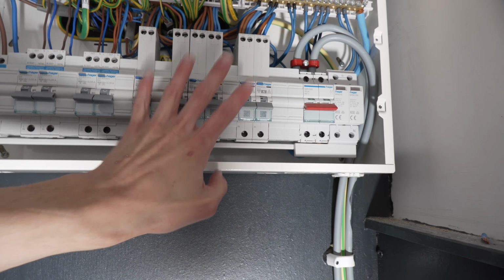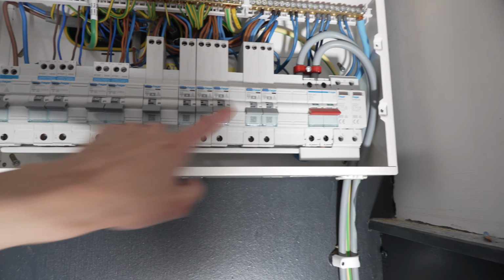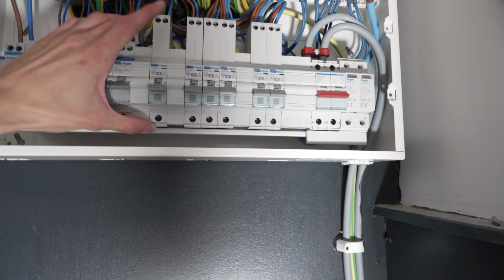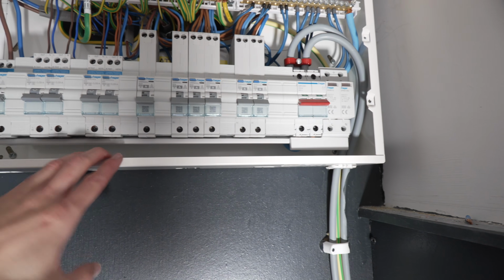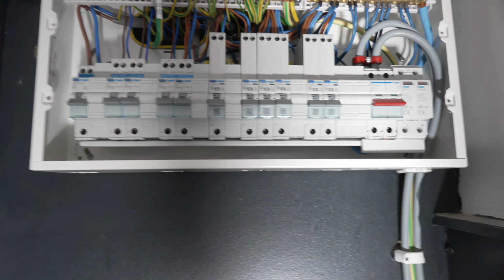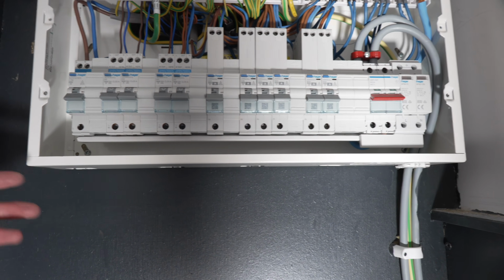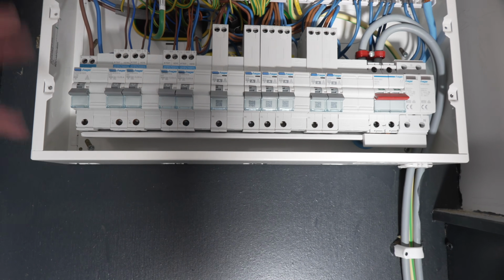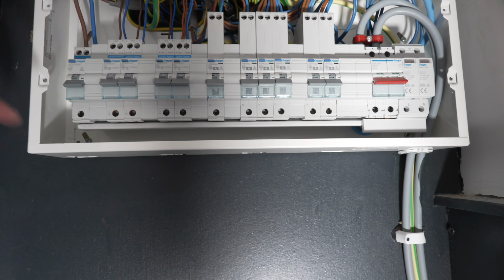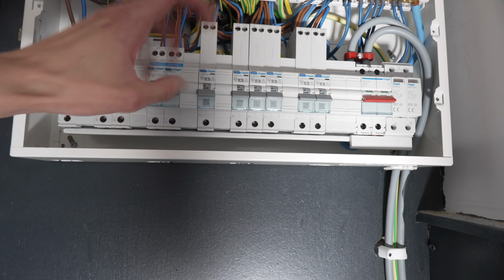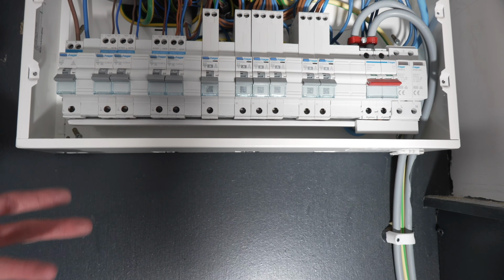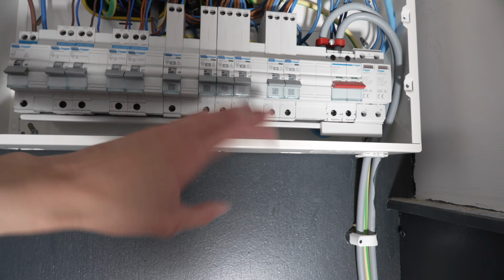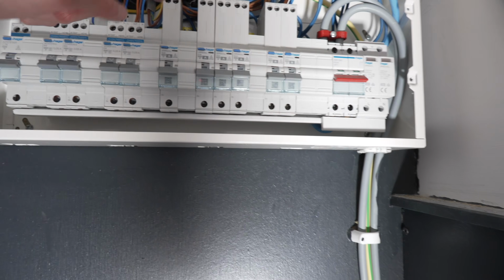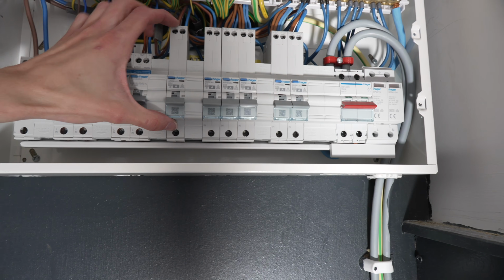The rest of the circuits are going to be a bit more awkward because I've got these AFDDs which are really tall. Really quite interesting, essentially they're arc fault detection devices, so they do everything a regular RCBO does, so overcurrent protection, residual current detection, or ground fault detection as you call it in America, but they also detect electrical arcing, like a loose connection or a damaged cable. So they're a good little device, pretty new, but quite cool. The downside with these is they are very tall.